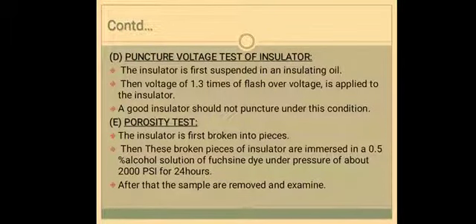Then next is the puncture voltage test on insulator. In this, the insulator will first be suspended in insulating oil. Then a voltage of 1.3 times the flashover voltage will be applied to the insulator. A good insulator will not puncture under this condition.